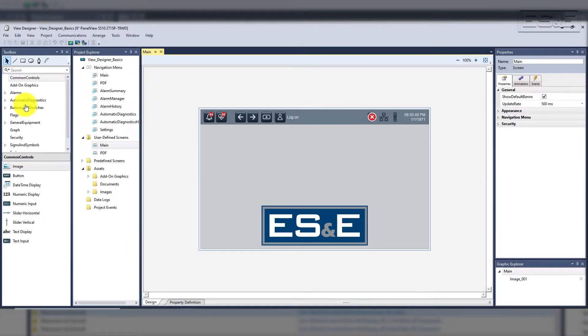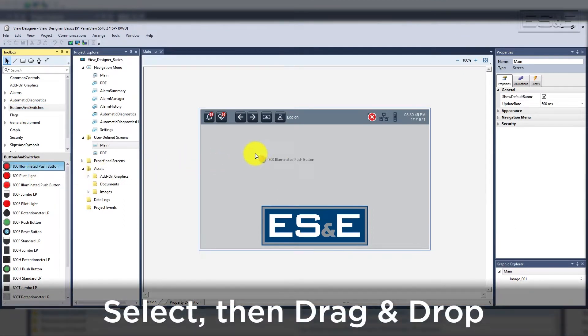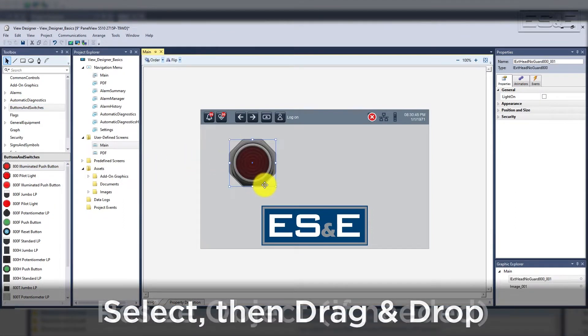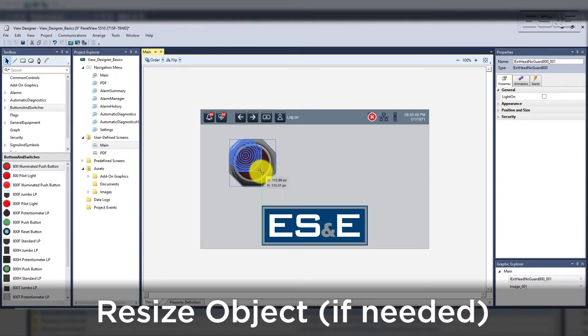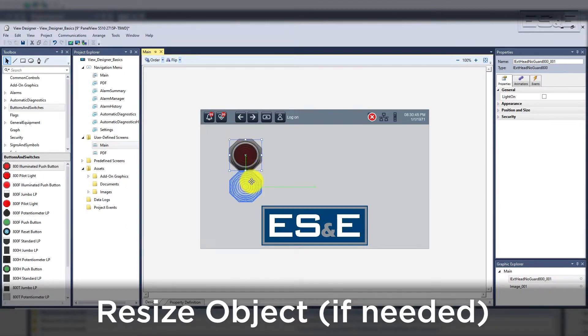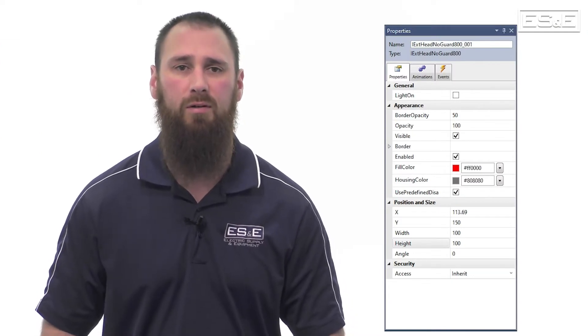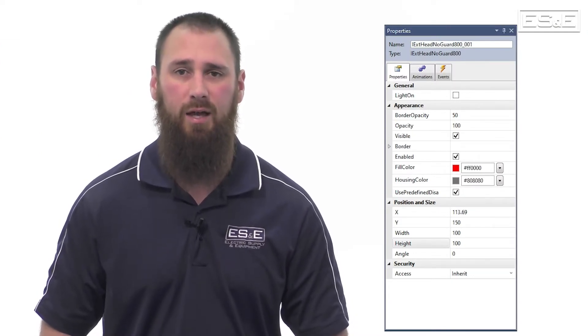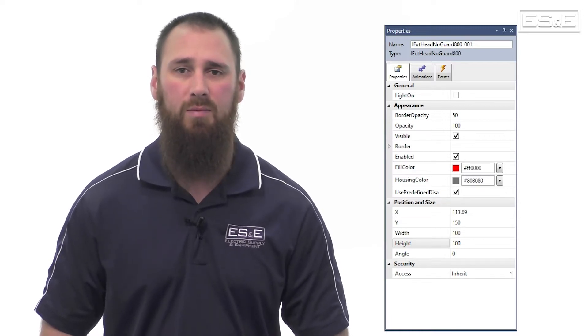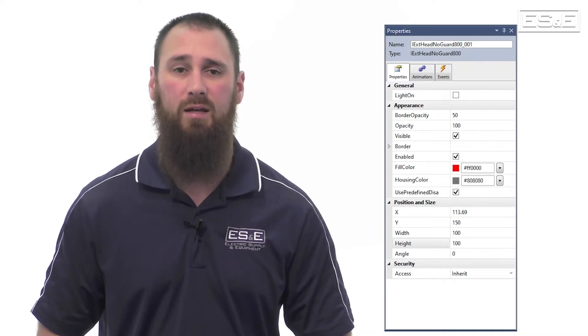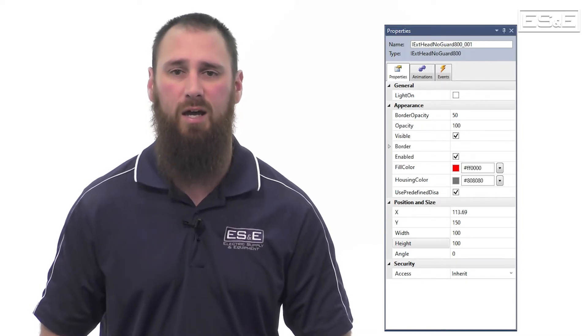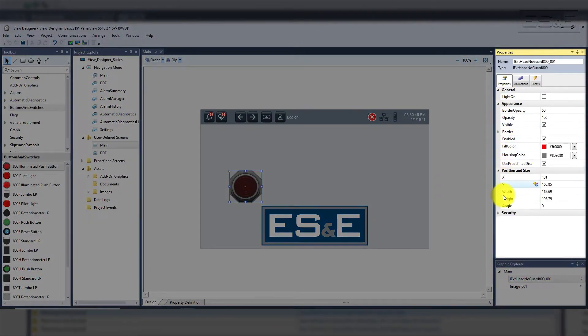The first object to add is a pre-built illuminated push button. Select the button from the toolbox and then drag and drop it onto the screen. Then resize the button — notice it has green indicator lines similar to Microsoft Visio or PowerPoint to help visualize sizing and spacing. Once the object is added, we will work on the properties found on the right-hand side of the window. In the properties window, you get General, Appearance, Size and Position, and Security Group options. These options are the same for all objects, but the properties inside each group will vary based on the specific object. You should check all the properties because you may not need to add your own animations for some objects.